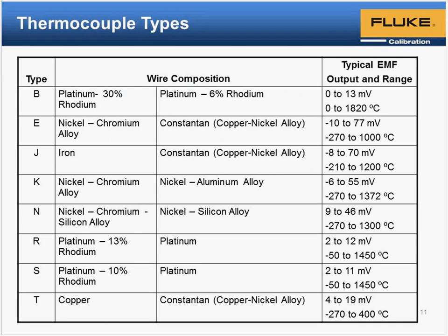Okay. The next question is about the limit on the resistance of thermocouples. Specifically, can implantable thermocouples have resistances of 180 ohms? Where's Steve? Right here. That's a good question. I haven't seen any literature giving the required resistance of the thermocouple insulation. We should take that into consideration and see if there are some recommendations out there, because some of the wires are so small.